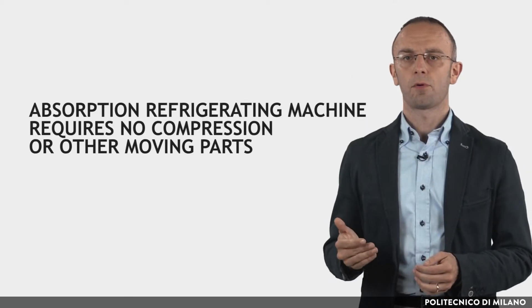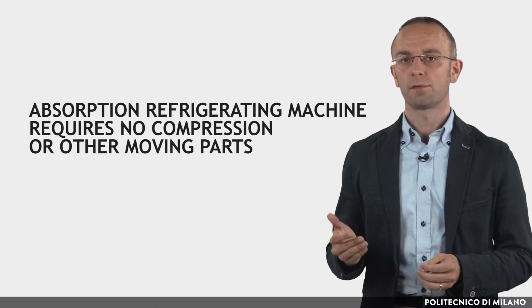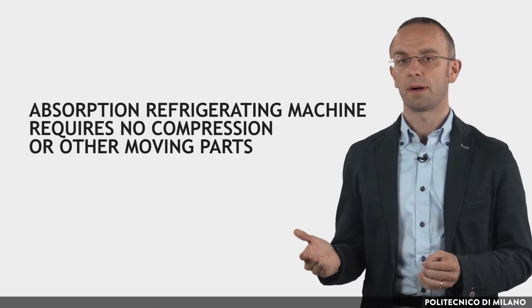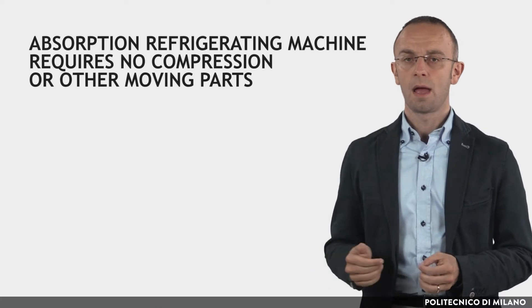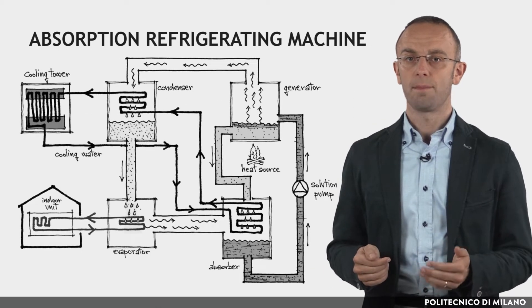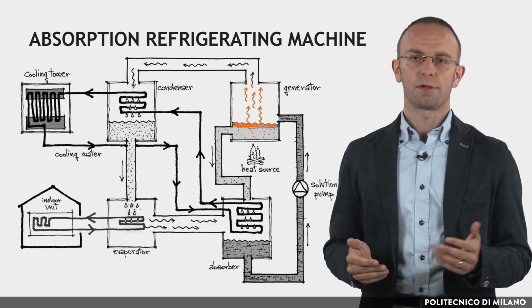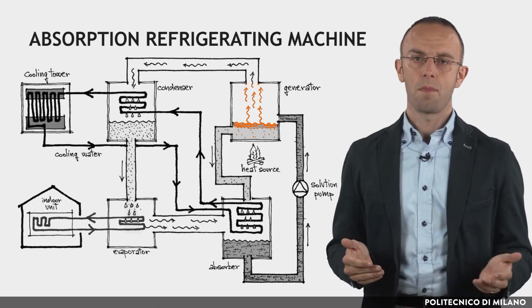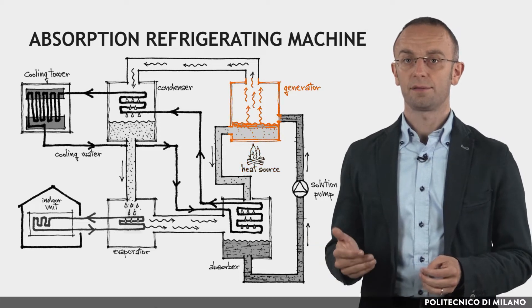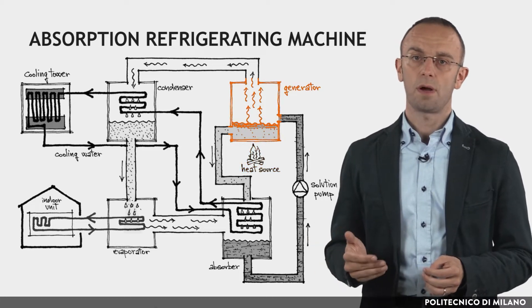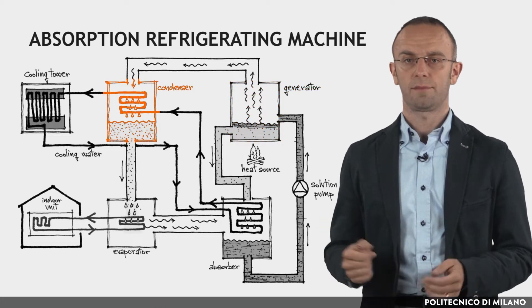Compared to the vapor compression chiller, the absorption machine requires no compressors or other moving parts to operate the thermodynamic cycle, but uses a source of heat in place of the compressor. A refrigerant solution, such as water-ammonia, is heated by a heat source in the generator, raising its temperature until it partially vaporizes and flows to the condenser.